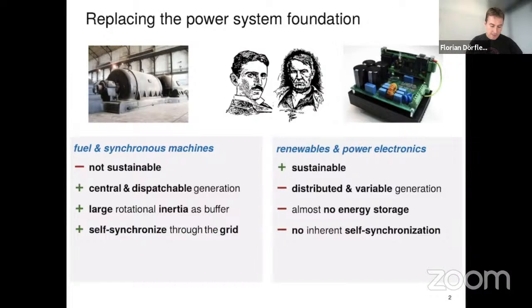As we heard in the last talk, synchronous machines are called synchronous because they synchronize—not globally, but within a rather large operating range, there's a stable, robust, purely physical synchronization mechanism based on clever design dating back to Tesla. Power electronics, however, don't do anything unless you control them to. There's no inherent self-synchronization, no stability whatsoever based just on physics.